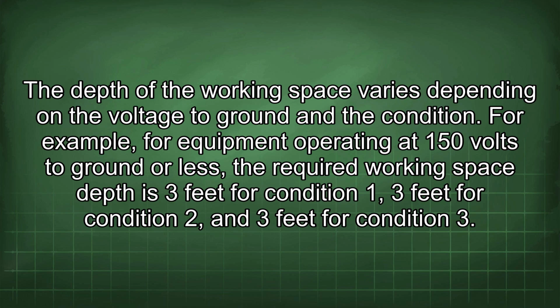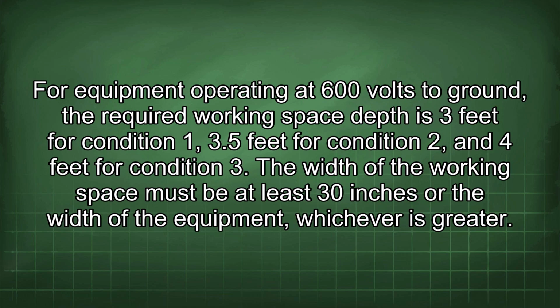For example, for equipment operating at 150 volts to ground or less, the required working space depth is 3 feet for Condition 1, 3 feet for Condition 2, and 3 feet for Condition 3. For equipment operating at 600 volts to ground, the required working space depth is 3 feet for Condition 1, 3.5 feet for Condition 2, and 4 feet for Condition 3.